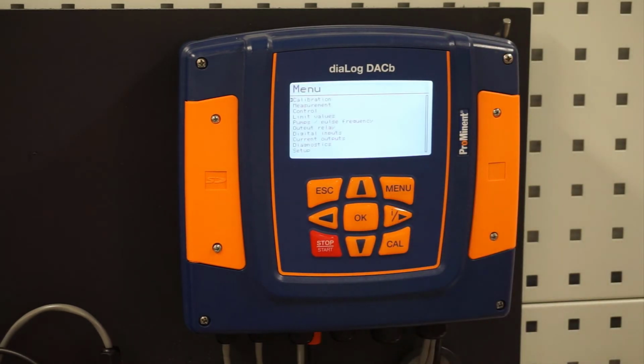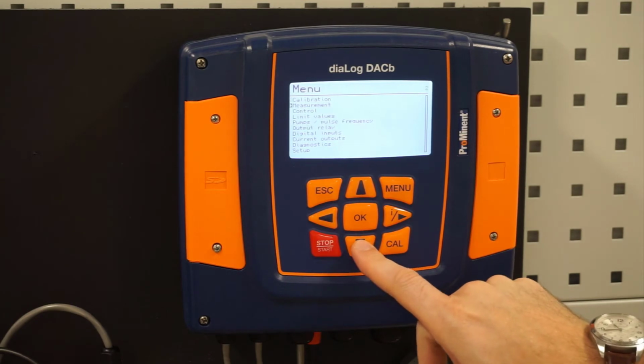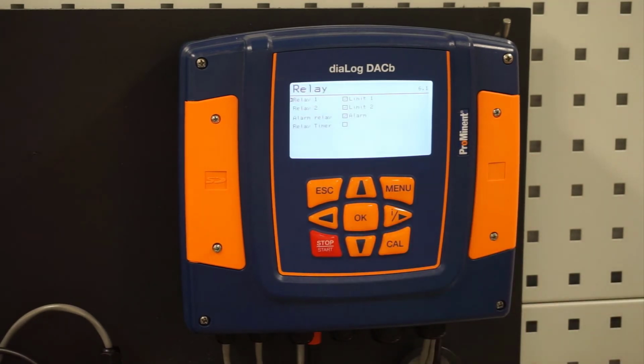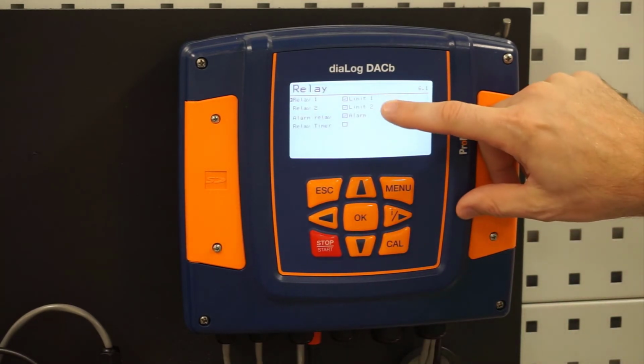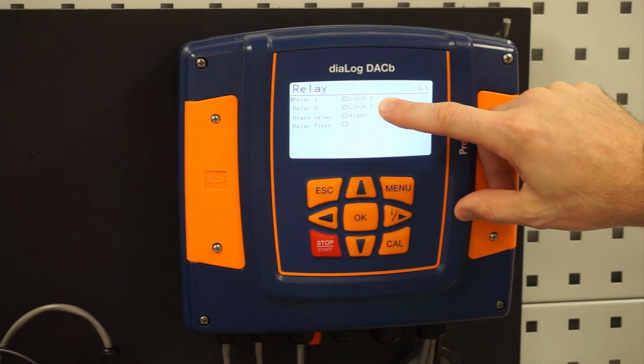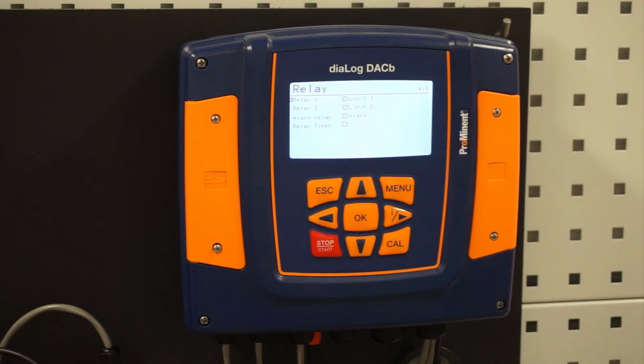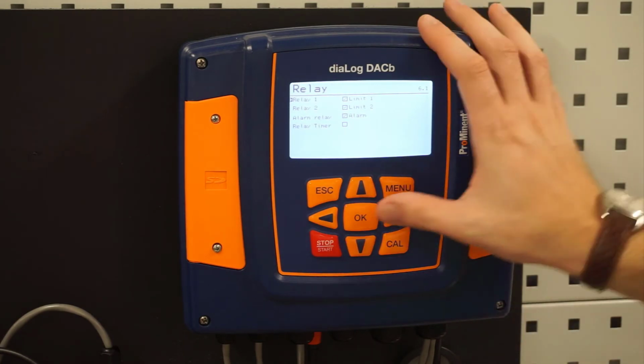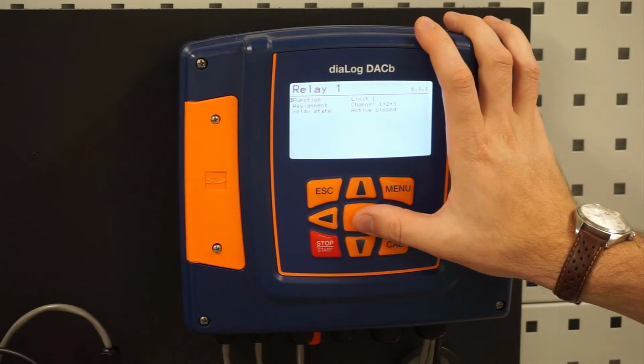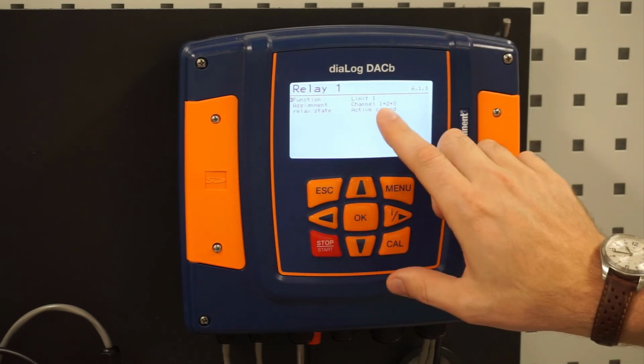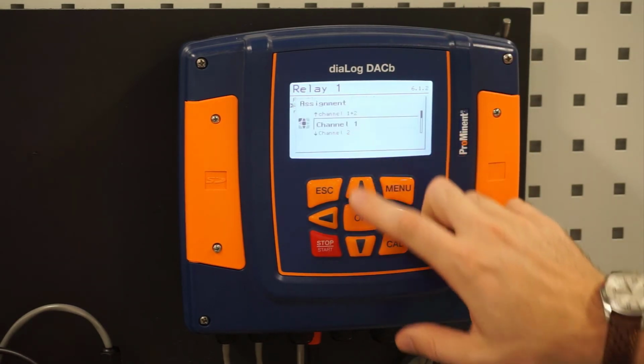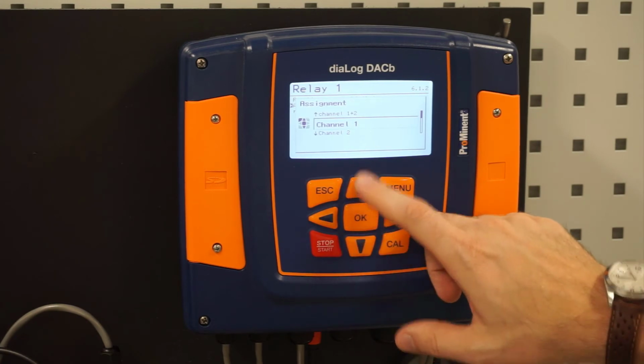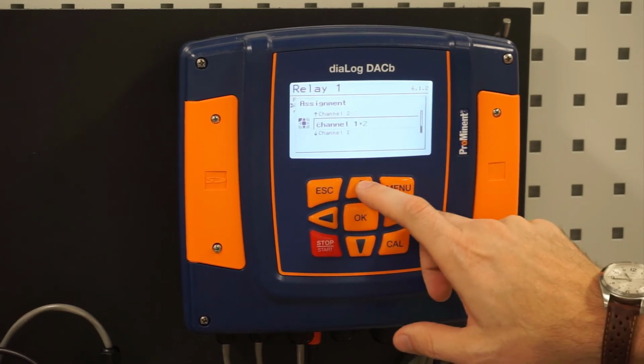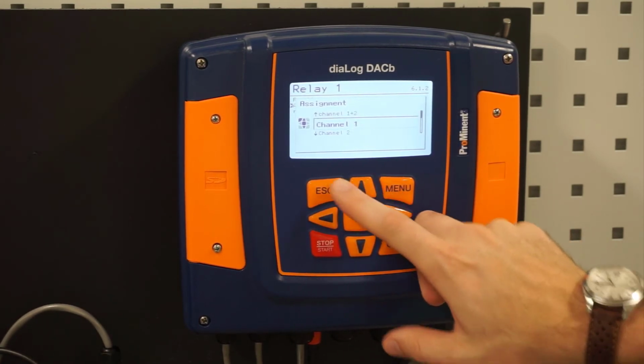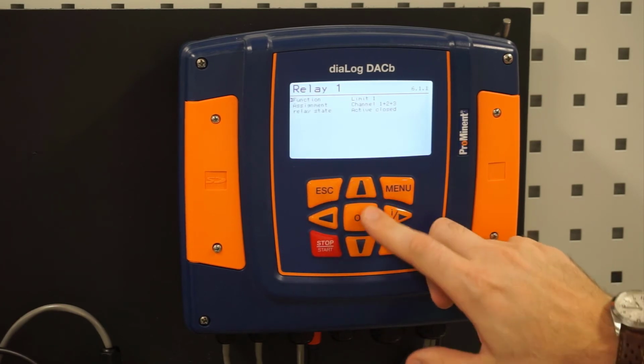I'm going to go to menu. Next is our output relays. So remember, we have 2 limit relays that we can set up. And then we also have an alarm relay. I don't have limits set up, so let's just go in there and turn it off. If I did, I can assign them to different channels. So maybe I just want it for channel 2. Maybe I want it for all 3. You can pick those options in here. I'm going to turn it off.